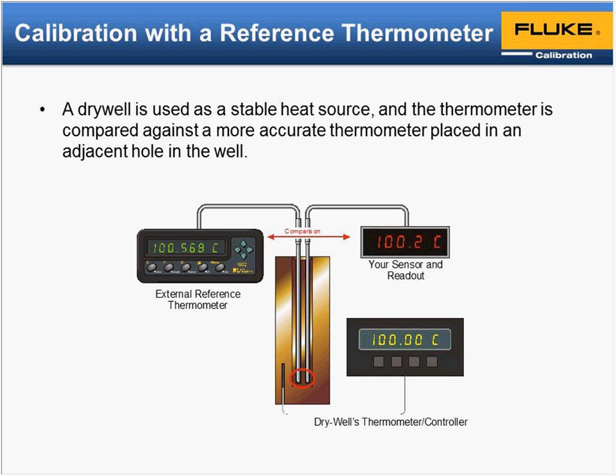Depending upon what equipment you may have access to, a lot of folks will have their gold standard, which may be the external reference and probe that they use in all of their processes, and then the heat sources become just a source of heat. The temperature of the heat source becomes a moot point, as it is a nominal setting, because we're actually going to be referencing to the known, which would be their external reference thermometer, which they consider their gold standard, and they will keep and maintain quality on those pieces of equipment.